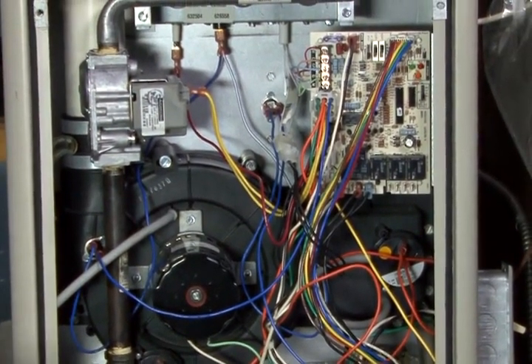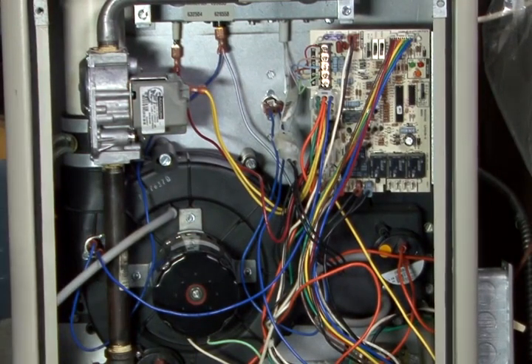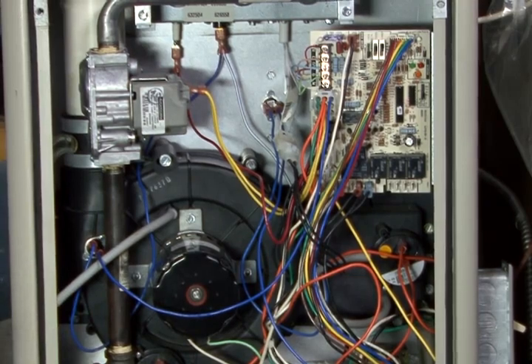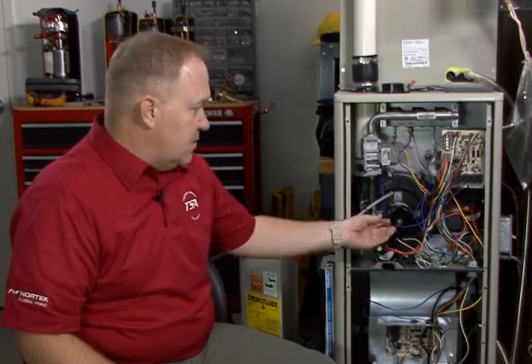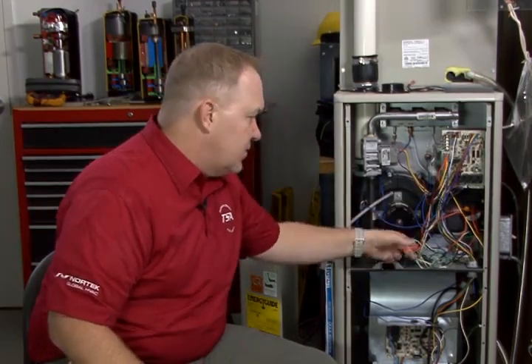As another example, in a two-stage furnace, if you know that the low fire pressure switch circuit is orange wires and the high fire pressure switch circuit is purple wires, when you recognize that on one two-stage model, it doesn't matter which model from that point forward. If you're looking at a 60,000, an 80, a 100, up to 120, those circuits remain the same. Also, as far as the limits or gas valves, things like that. So when you begin to recognize those circuits and what they are by color, in our product line you can move from one model to the next, open them up, and very quickly, very efficiently, and very easily identify, okay, these are my limits, this is my pressure switch circuit, and it will help you make your way through the inner cabinet and the wiring very quickly and very easily.